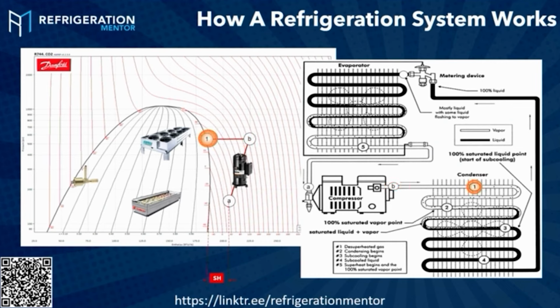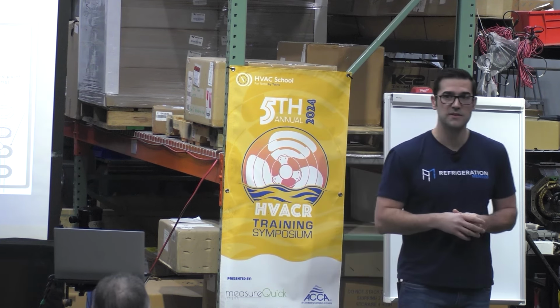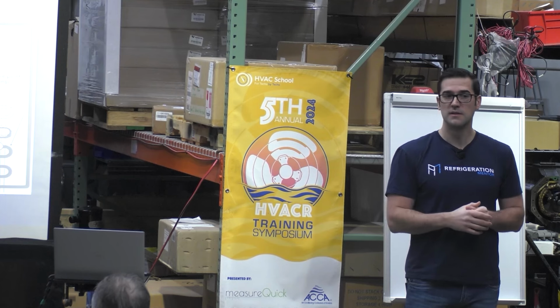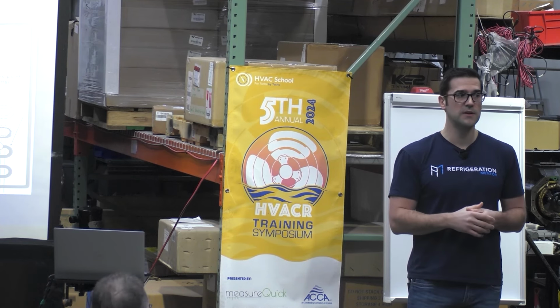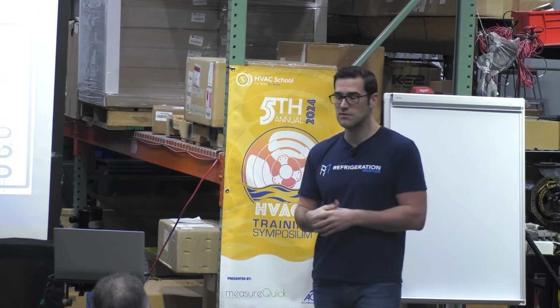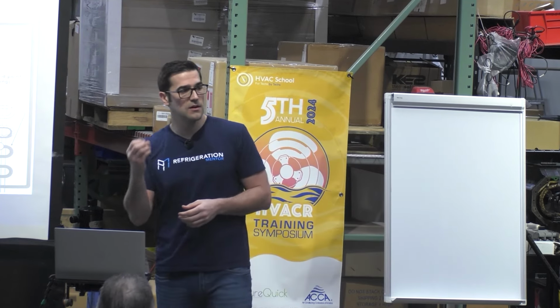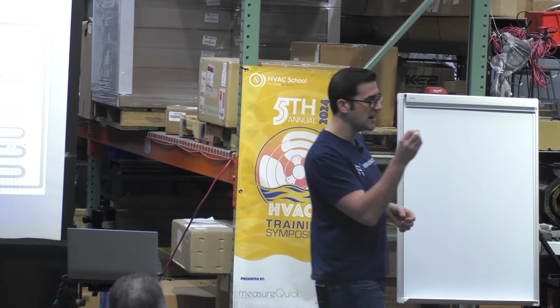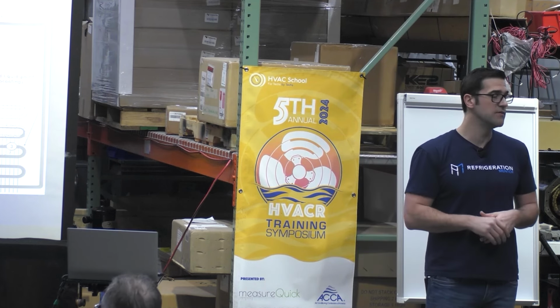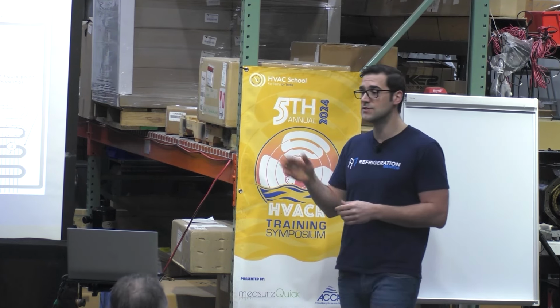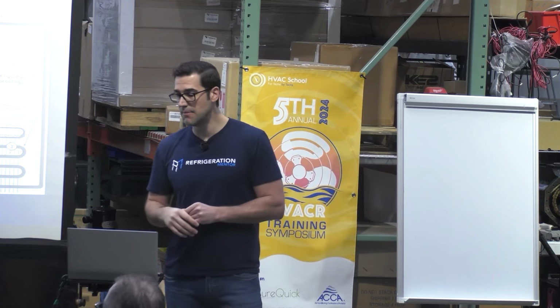This point here is called what? Does anybody know what that's called when we hit that point on a Mollier or a PH diagram? Where one is the black line that comes down the curve? Saturation point. And there's a specific name that I call it. Dew point. Anybody here ever hear of dew point? Saturation, you're right. So this is right when that vapor starts to have little droplets of liquid coming out of it. And this is where the condensation starts, or the condensing starts to happen. So this is your dew point.